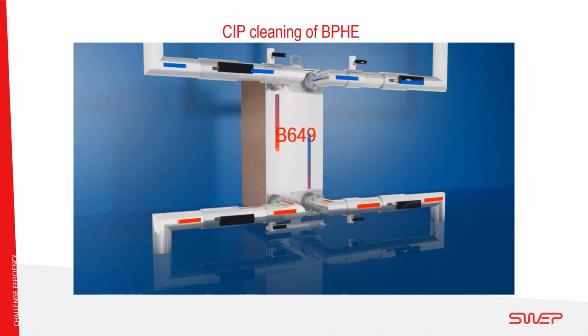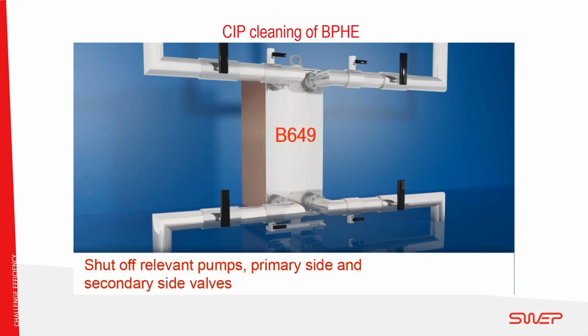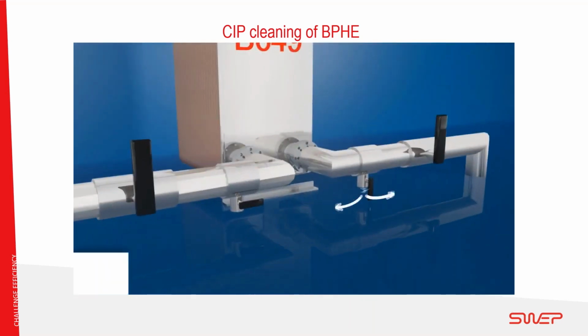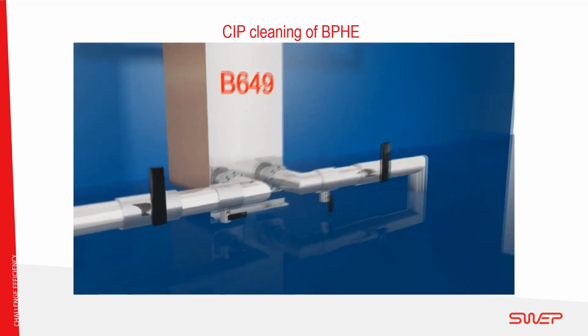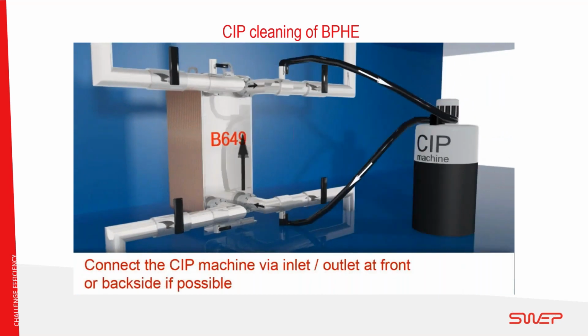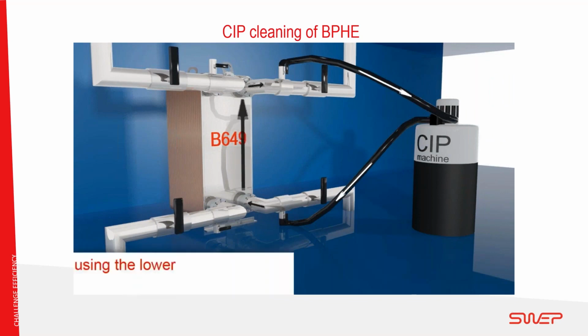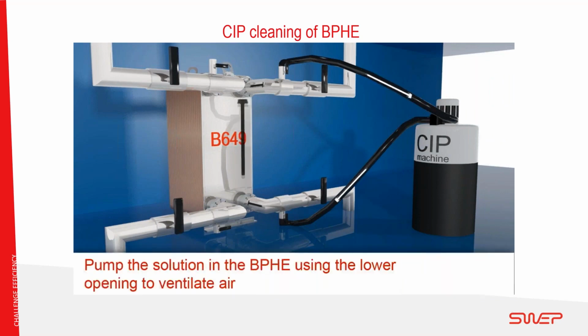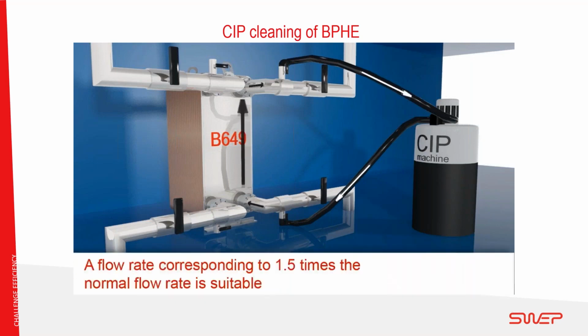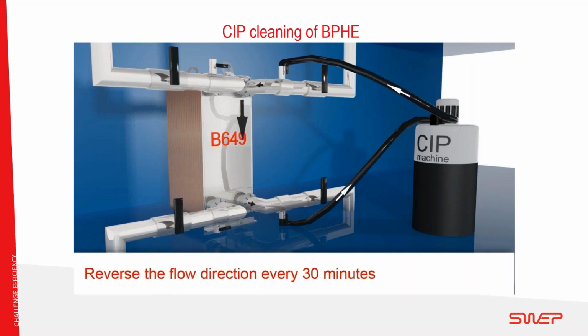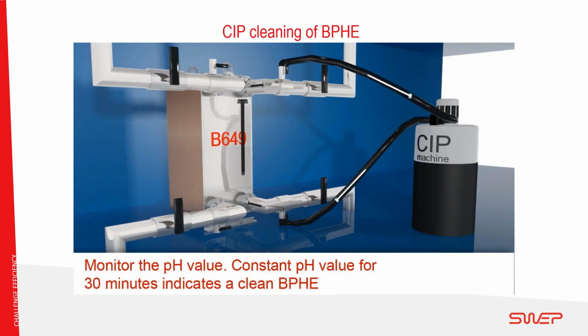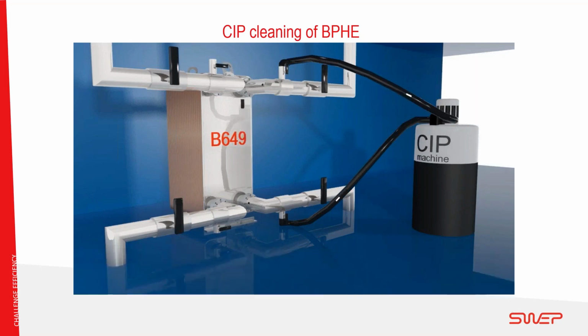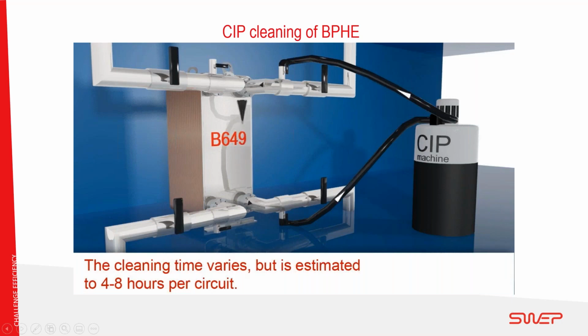Another question we get asked is cleaning of heat exchangers. So in this short video here, you'll just see how that's addressed. Again, brazed units can't be stripped, but our philosophy is that we would always push people down the road of cleaning in place. Of course, there needs to be some valve and tapping configurations put in. An option could be to actually just remove the heat exchanger and put it to one side and do the cleaning in place that way. But it's a very effective solution. Of course, there's no requirement for stripping, regasketing, the associated cost and labor involved in doing that.